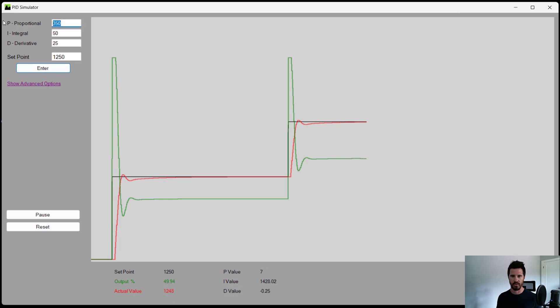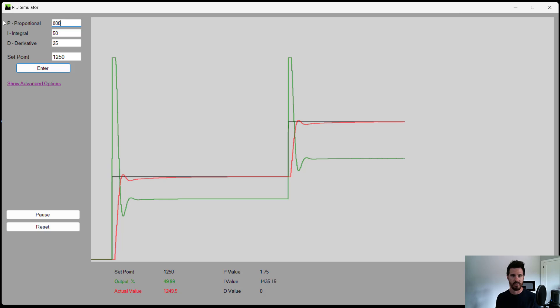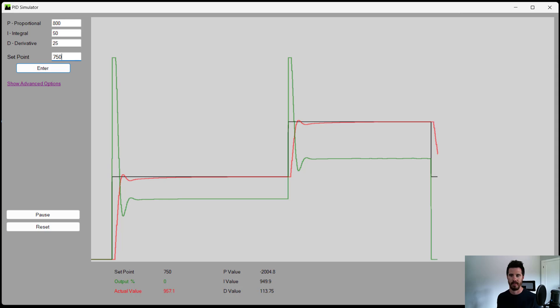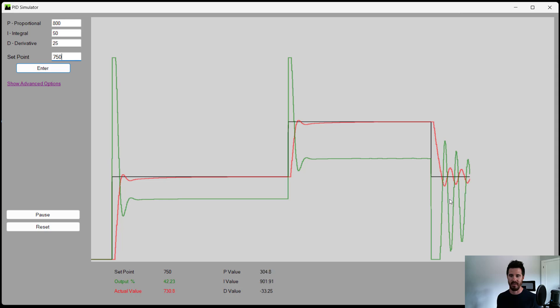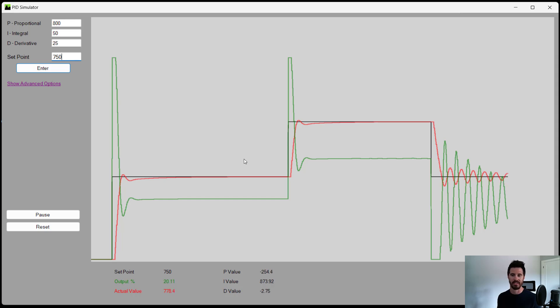Now say we want to tune this controller to be faster, even though why would you ever, because it's a perfect acting controller, but I want it to be faster. So let's put our P value at 800 and change our set point again. Notice how the proportional is very fast acting on that output, holding it way above and way below the set point, causing oscillations and an unstable controller.